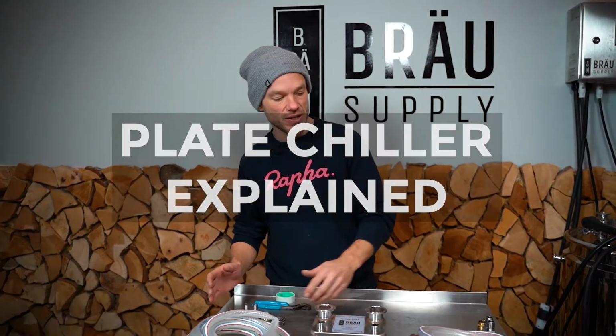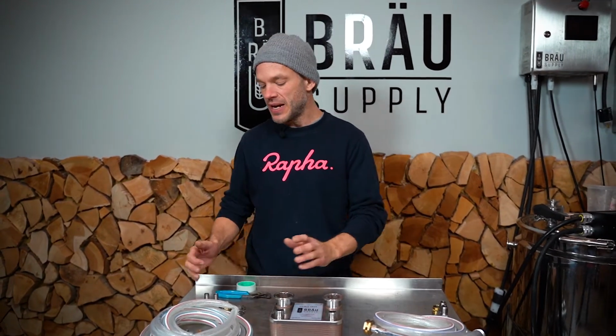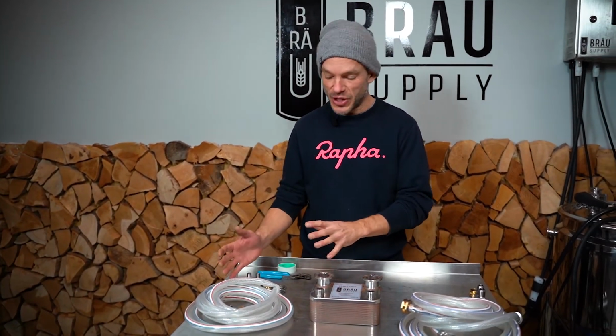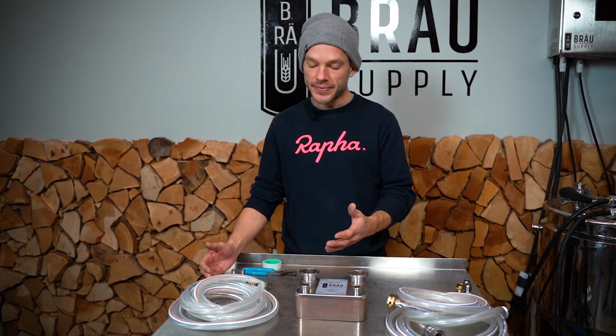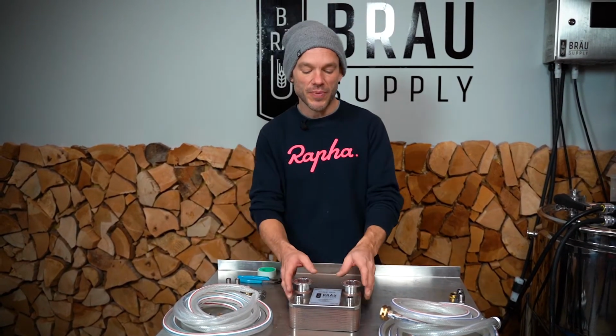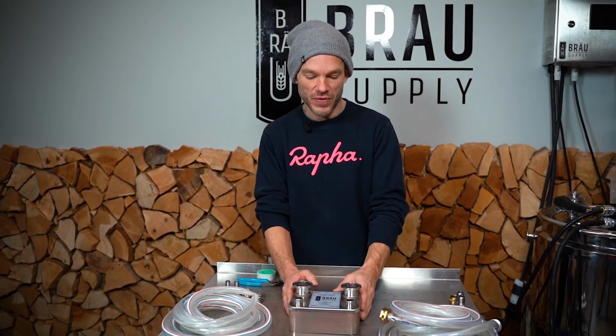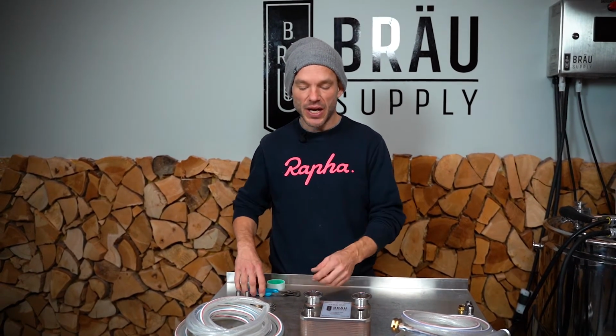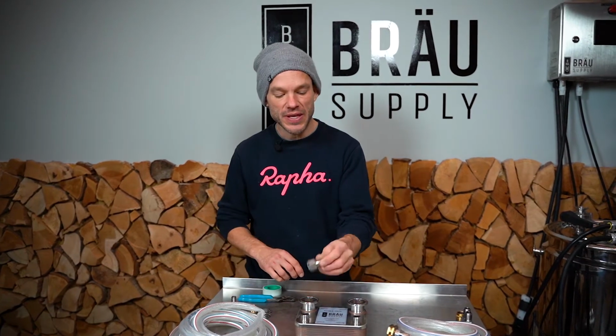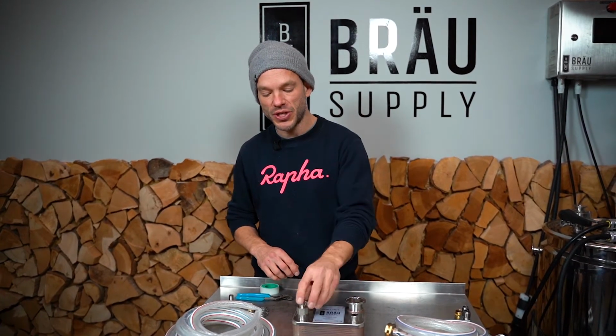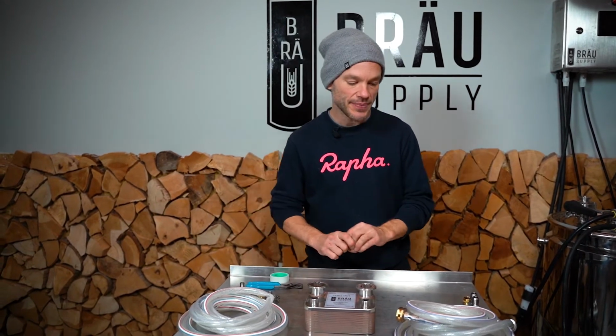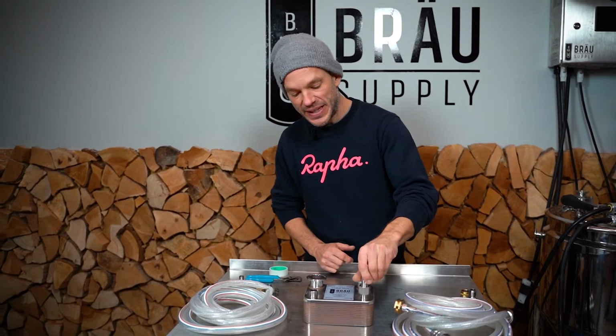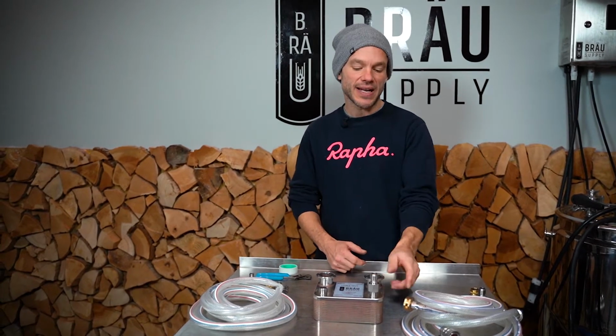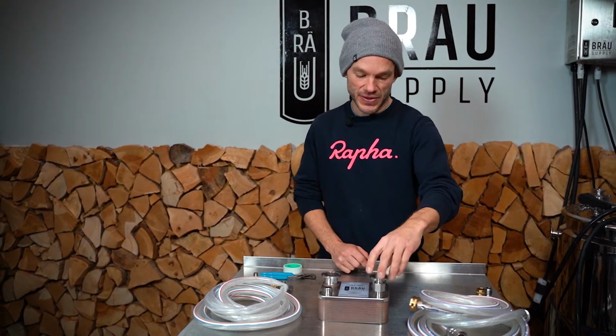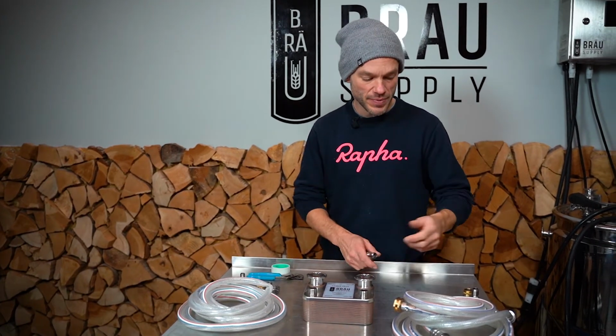The chiller comes on its own or with the basic connection kit or the quick disconnect connection kit. The basic connection kit is a little bit cheaper, but it doesn't disconnect from the chiller, making sterilization more of a challenge. You have to manually use a wrench and unscrew the barb fittings which connect onto the chiller. For the quick disconnect kit, you leave the quick disconnects in place, and you can sterilize this in the oven just by removing it.